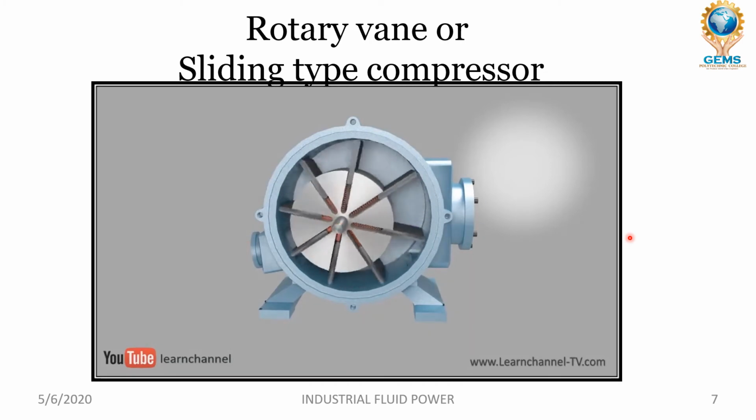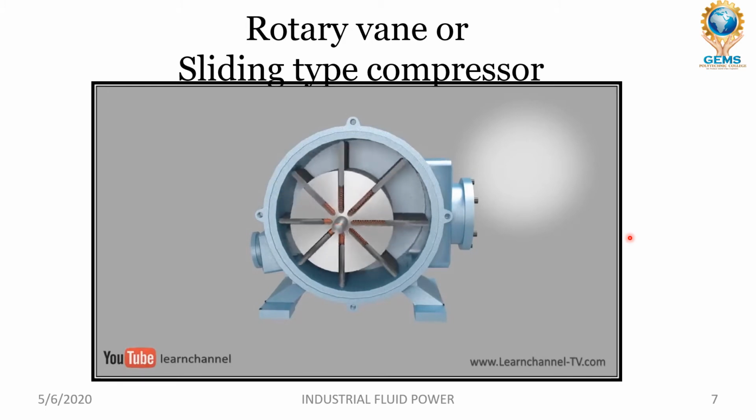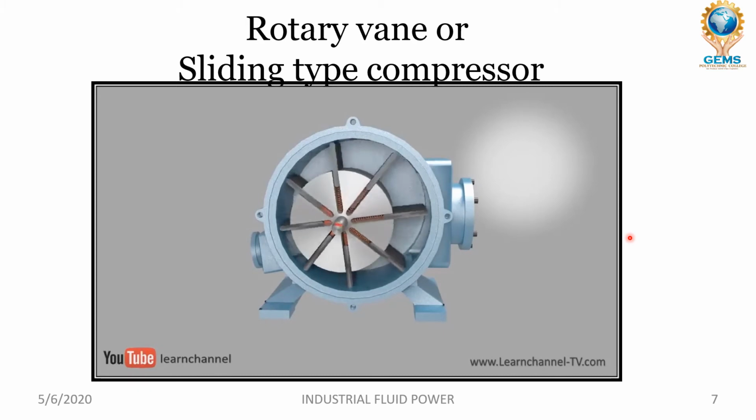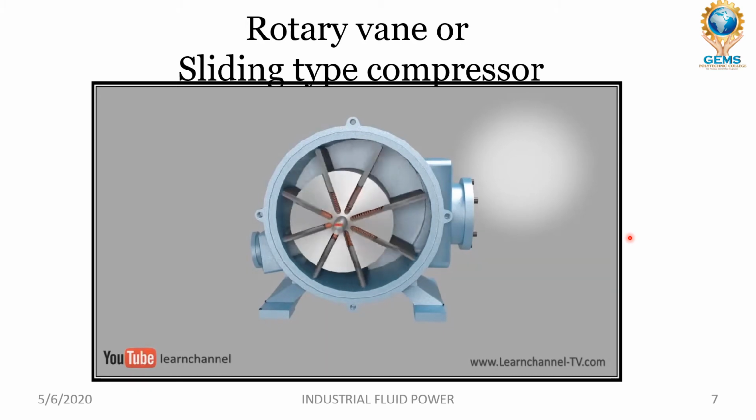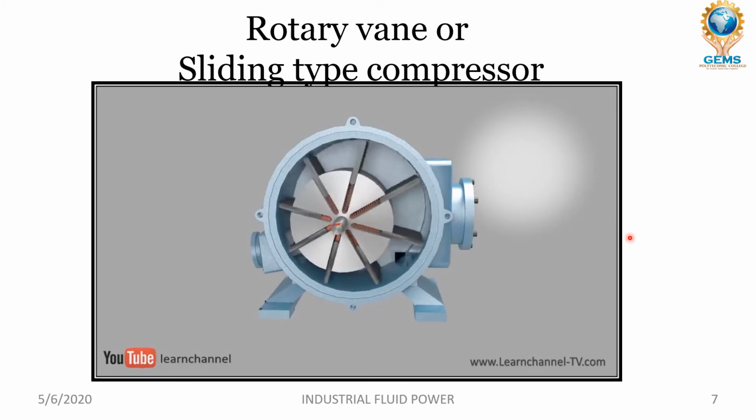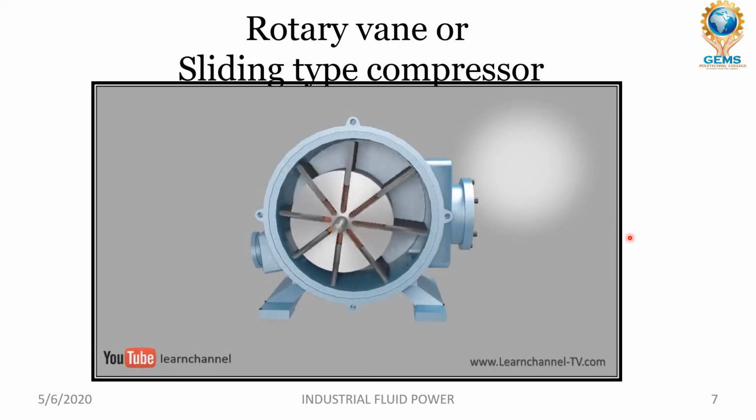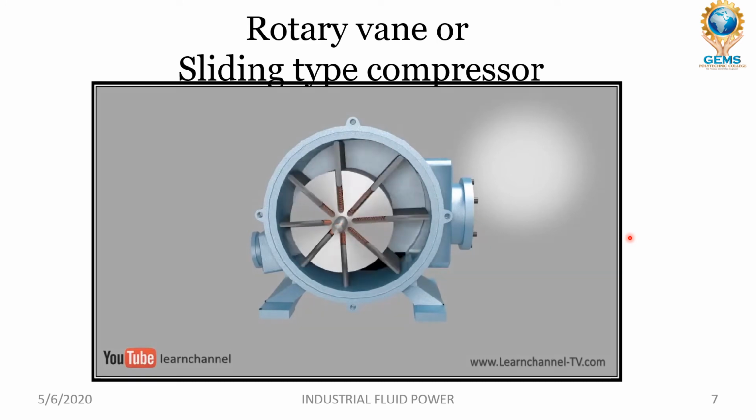Advantage here is the pulsation-free flow, in contrast to piston compressors. Therefore, an air tank may be optional. In addition, these compressors are quiet and relatively insensitive to dirt. Typical applications are, for example, wastewater treatment, fish breeding aeration, dust collection, vacuum packing, and so on.